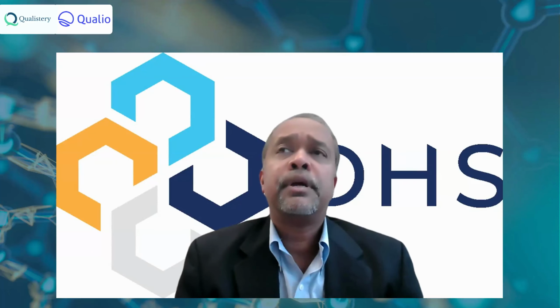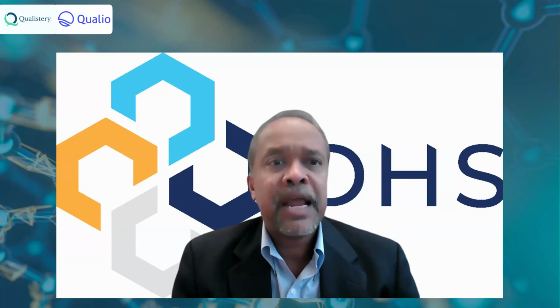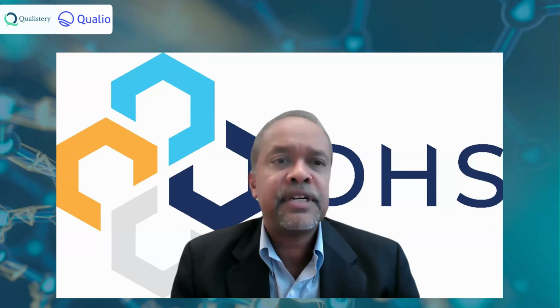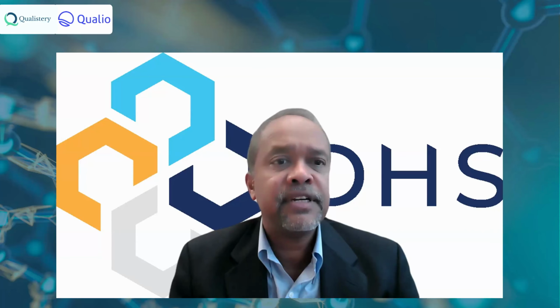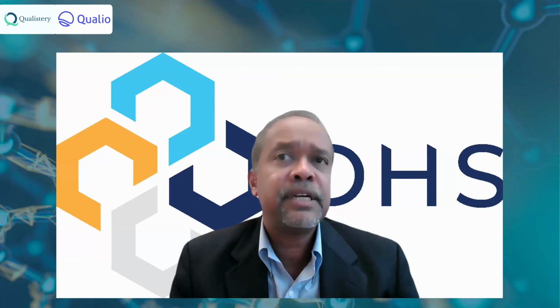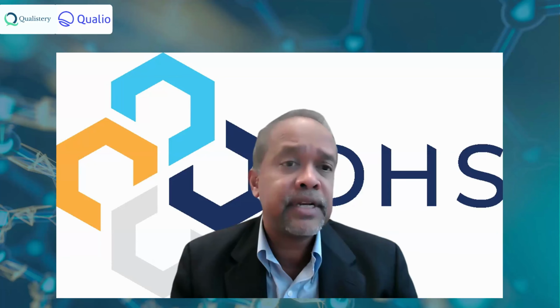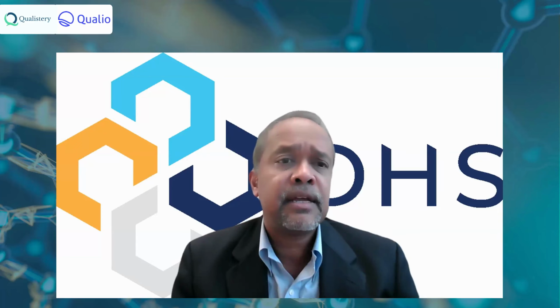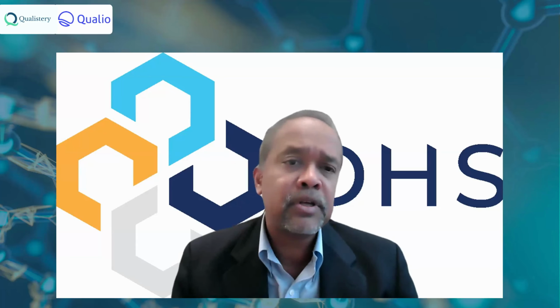The next question that we have is, how would you recommend controlling security standards in SAMD, software as a medical device, if you're using them? So, you need to make sure privacy concerns are addressed about your SAMD, right? That's very important. Besides the safety of the device. So if it's a SAMD device, your responsibility is for ensuring all the usual things. Design control processes may be aligned with 13485. Those apply, right? Your 62304, it's software.